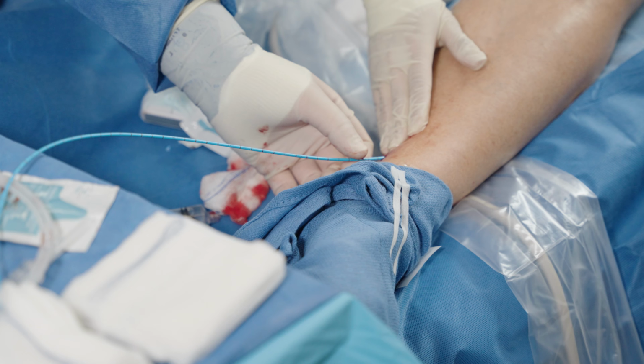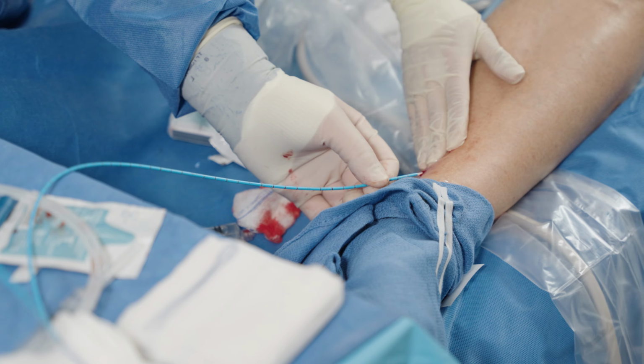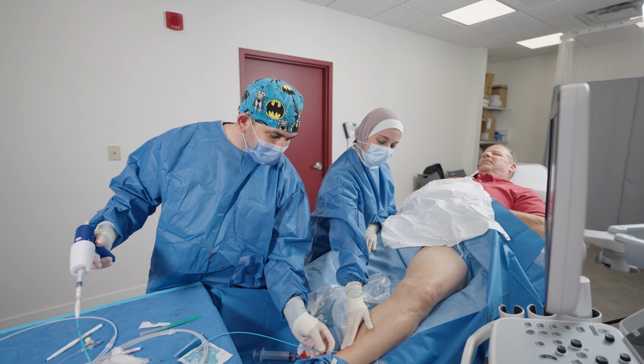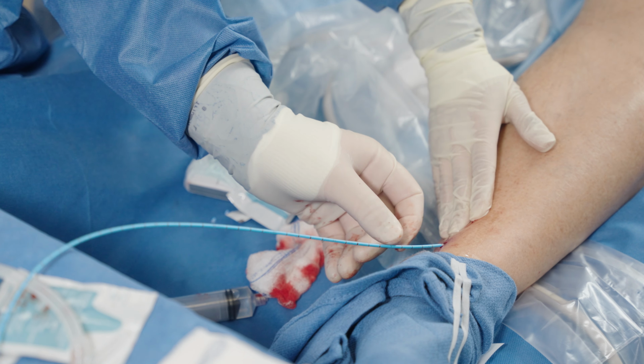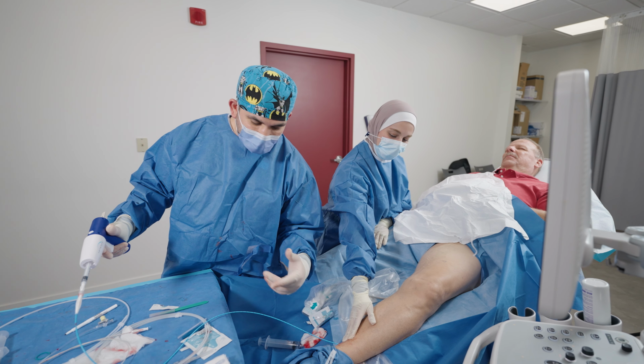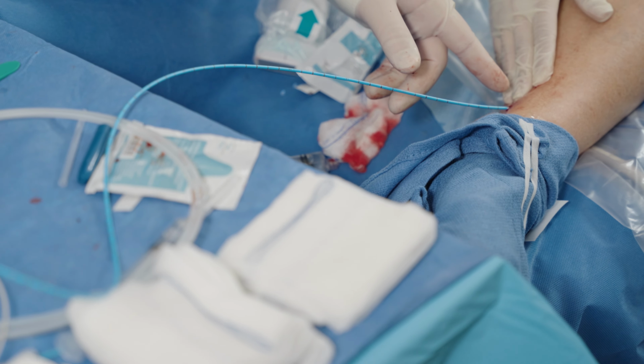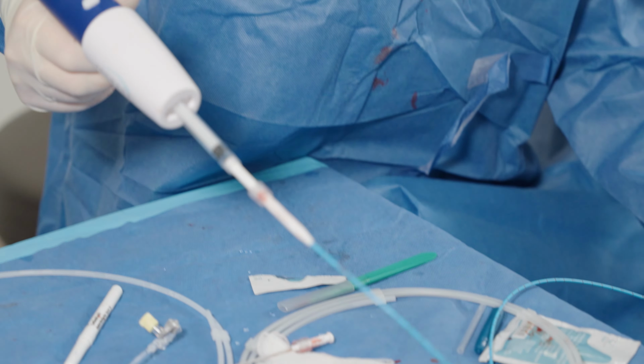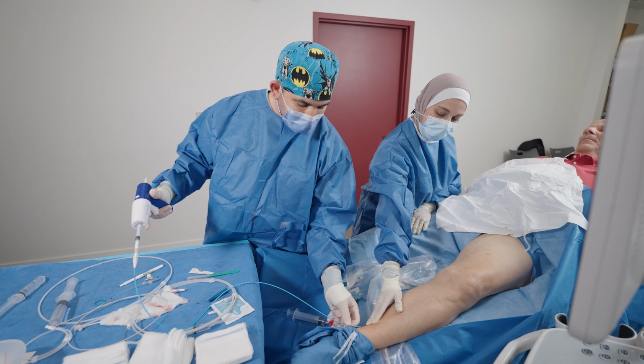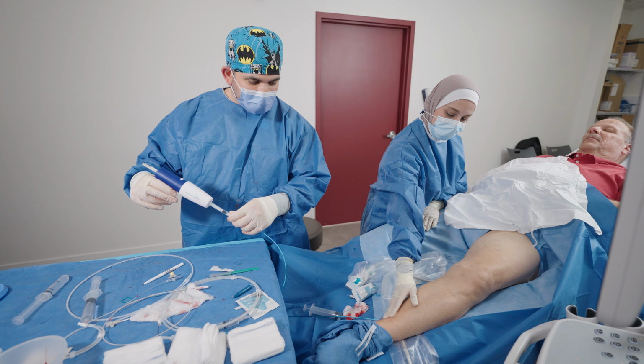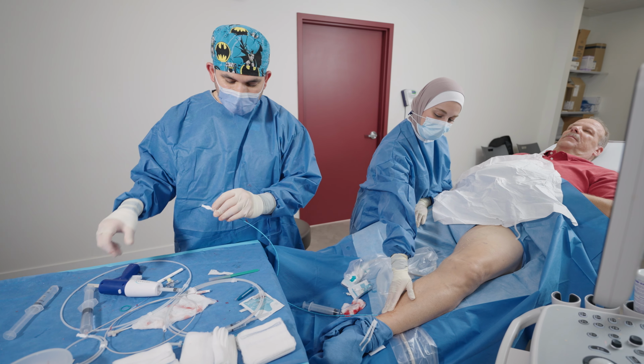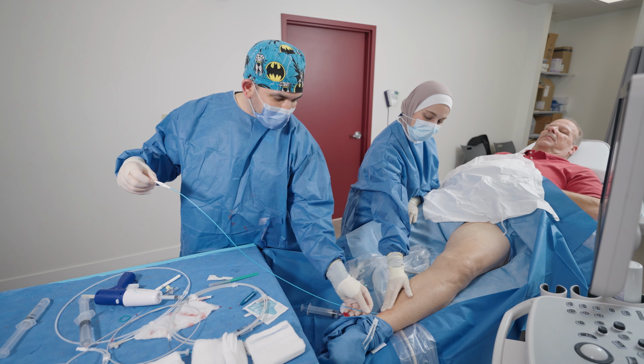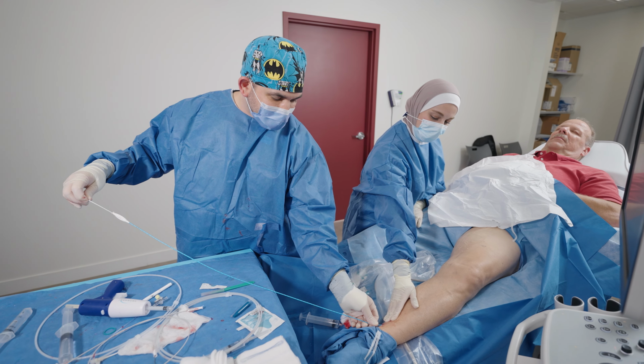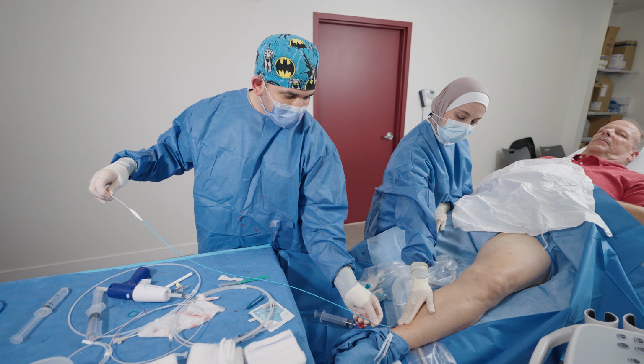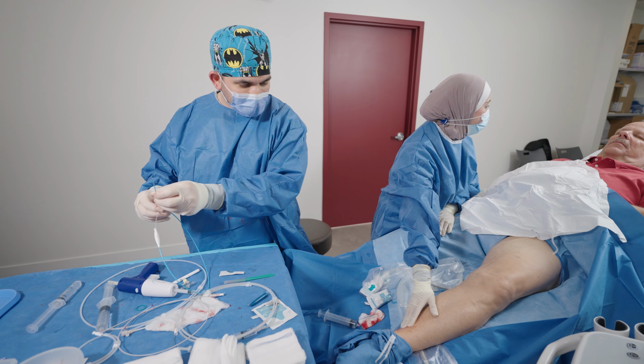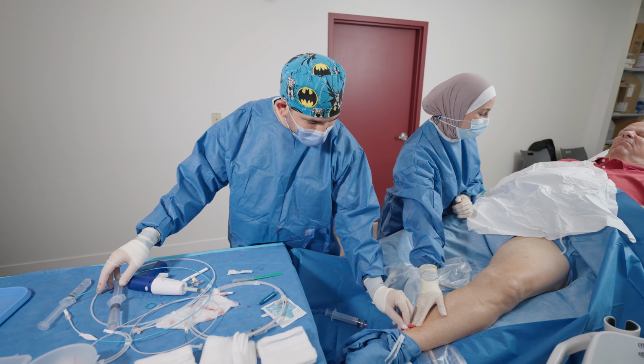We're at the end of the procedure now. So you can see there's still the clear part of the catheter, which protrudes 5 centimeters from the end of the sheath, which means that we can still deliver 1 aliquot of the adhesive into the leg. Hold it for 3 seconds, and release. And then we can disconnect from the syringe, advance the sheath back over the catheter so that there's no glue deposited outside the vein. And the glue comes out.